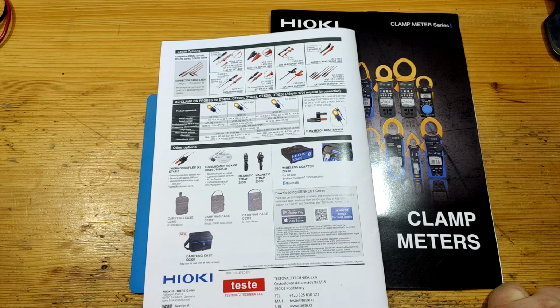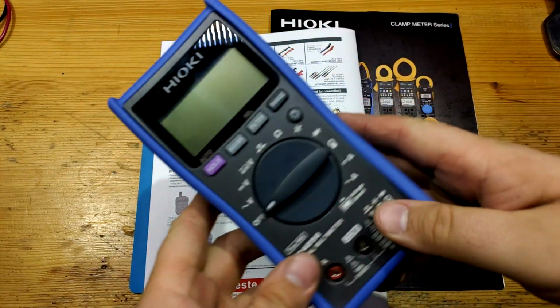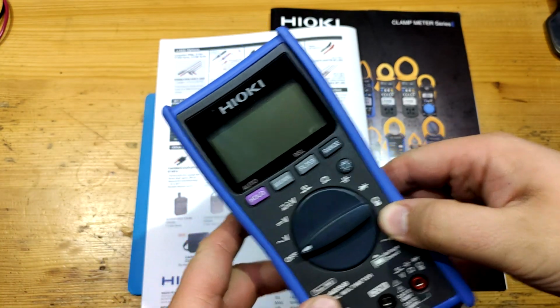You can also connect passive clamps on the current range as long as it's shorted by the internal fuse, and you can put protective anti-parallel diodes in the clamps, and you're pretty much good to go. There will be no problem connecting clamps to the current range, just adjust the ratio on the multimeter, and boom, you can save this range for anything else.